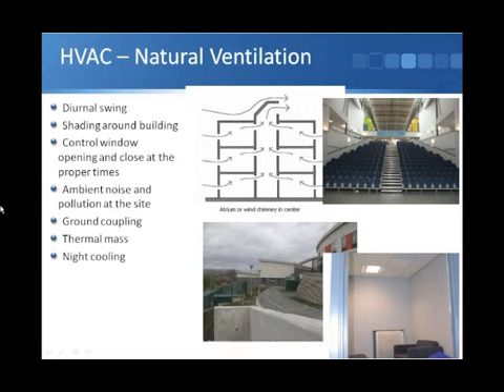And if we're going to use natural ventilation, we need to understand how to deal with diurnal swing. How does the temperature over a 24-hour period change? So if we have a sinusoidal swing, so that we have a hot day in the summer, but in the evening and the night time that temperature drops, we've got a chance for the building to recover. We can use that cool nighttime air for night cooling. We need to think about shading very carefully. We think about how to control window openings. Natural ventilation may want opening windows.